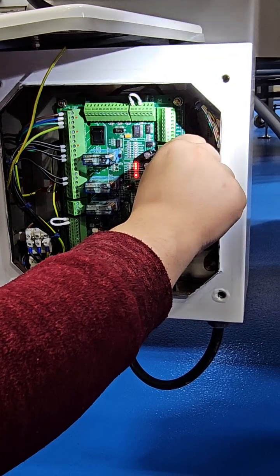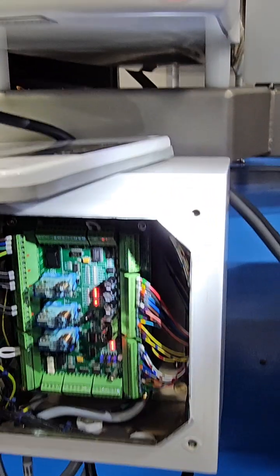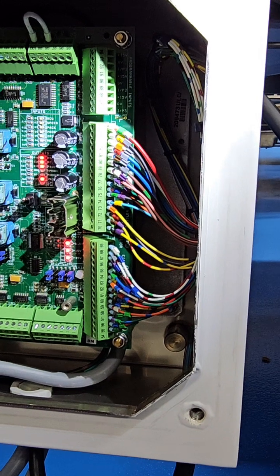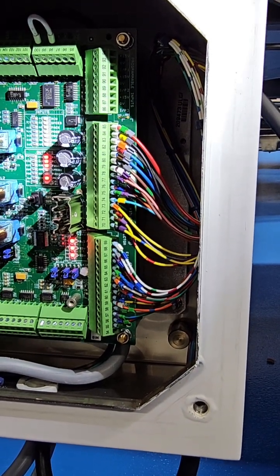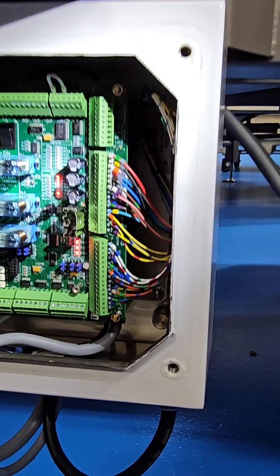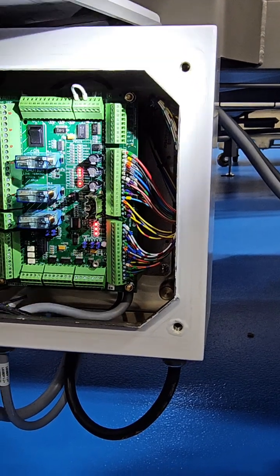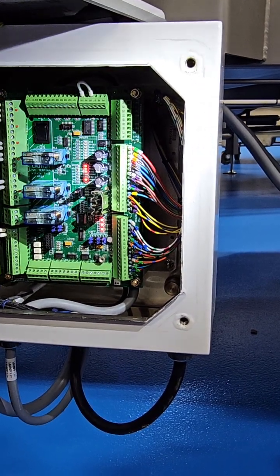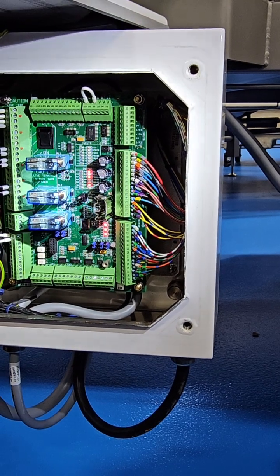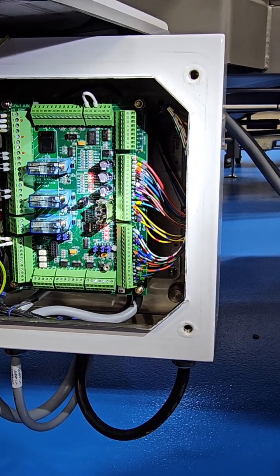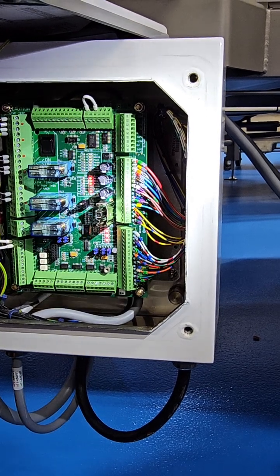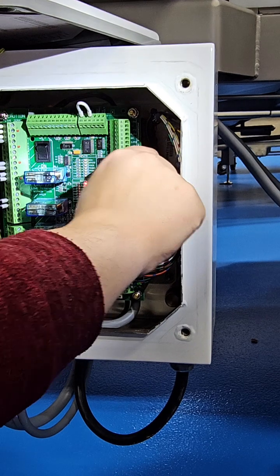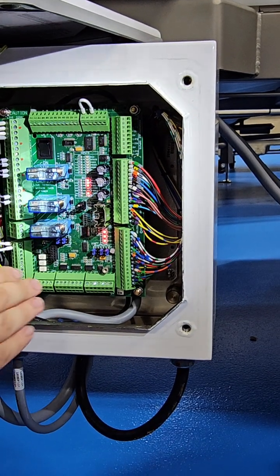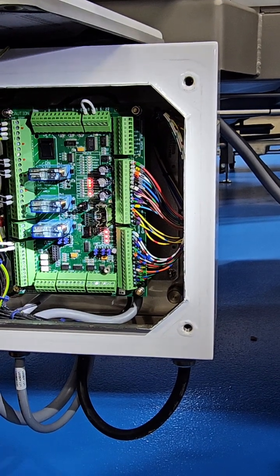Our two 15-volt wires, red and white, are biasing voltage to the receiver coils in the head. Those voltages have to be opposite of each other and within tolerance for the machine to function properly. If they get too far from each other, you'll start getting yellow or red screens, and if you get errors, you can come down and check those two. If either one of them is out of tolerance, you need a new power supply. Super easy.